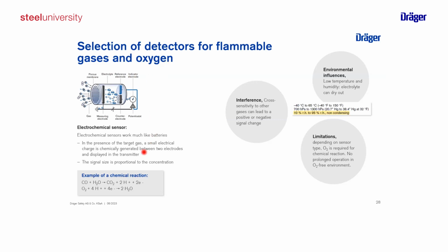Important on this, and this is shown here by the chemical reaction below, as an example with CO. What always happens is the gas is coming into, or vaporized into, the sensor, and you will always have a liquid. In this case, it's the water inside, always combined with an acid or with salt. And we will have a reaction of the CO with the water, forming CO2. And important, what we see is we create the electrons. On the counter electrode, we have the opposite reaction, that the electrons are recombining with the oxygen. So we have a closed process. What the sensor is measuring is not the CO or O2, it's measuring the electrons. So we generate electrons, and this is a proportional indication of the gas which is oxidizing or reducing. So that means our measure is not the gas itself, it's a part of the process.